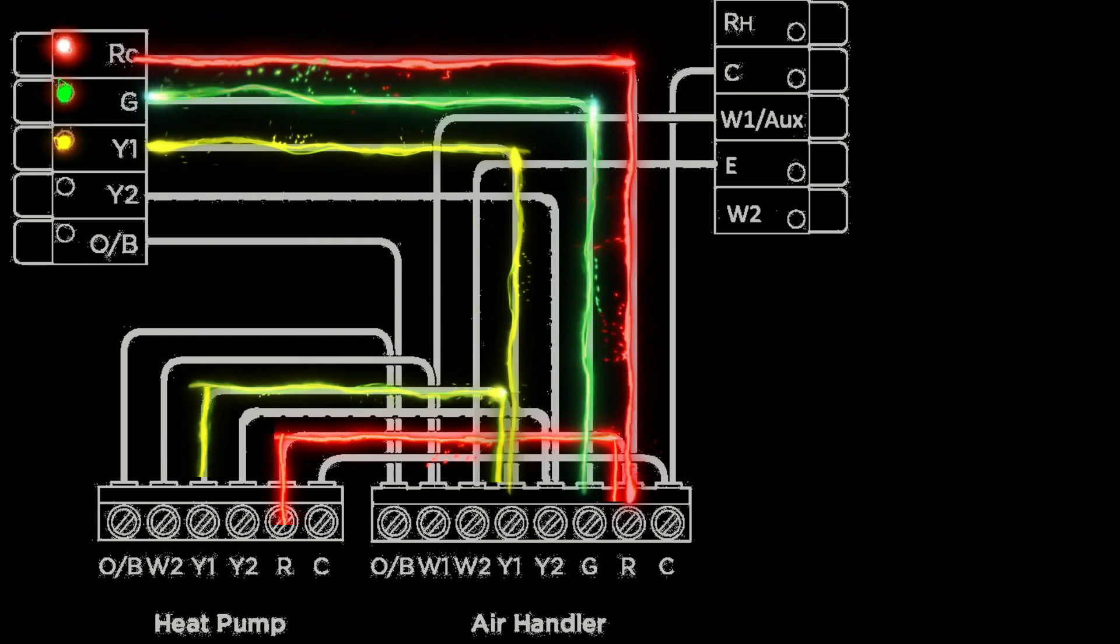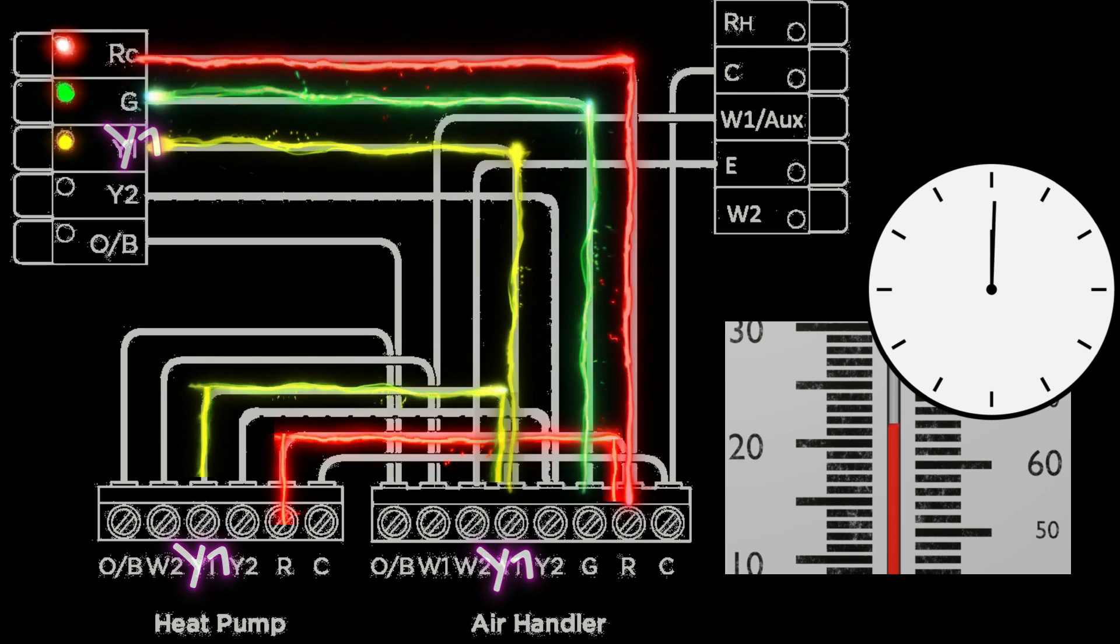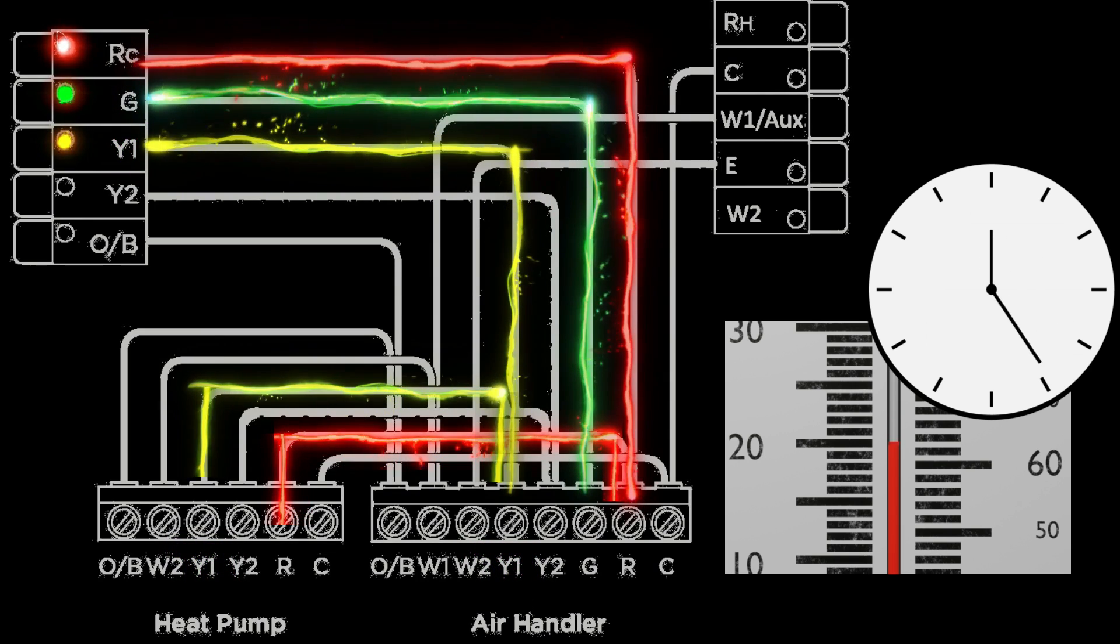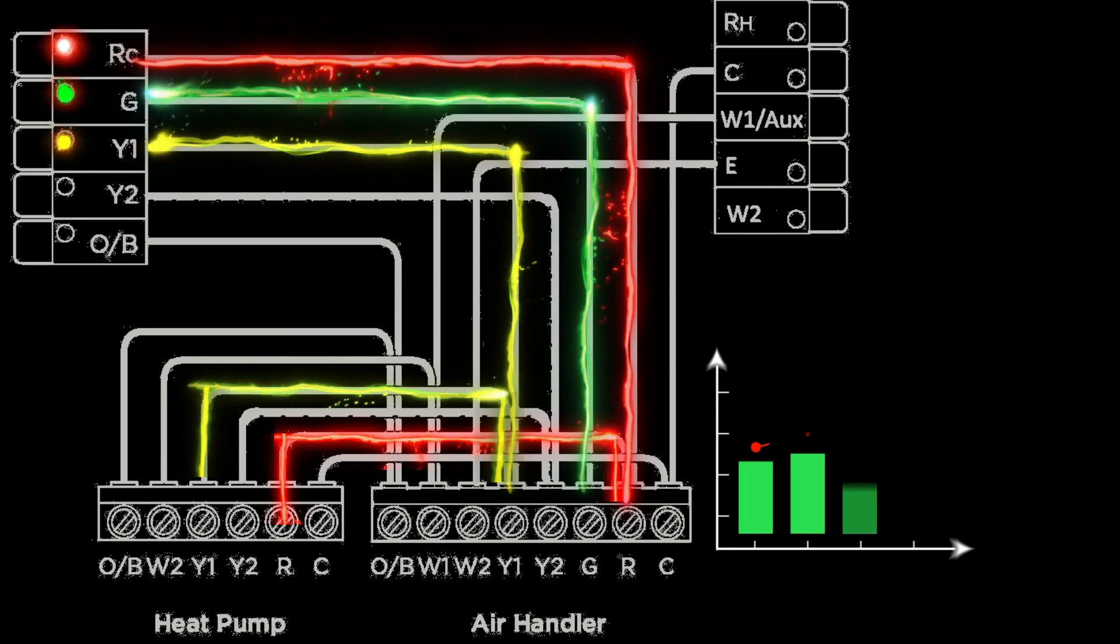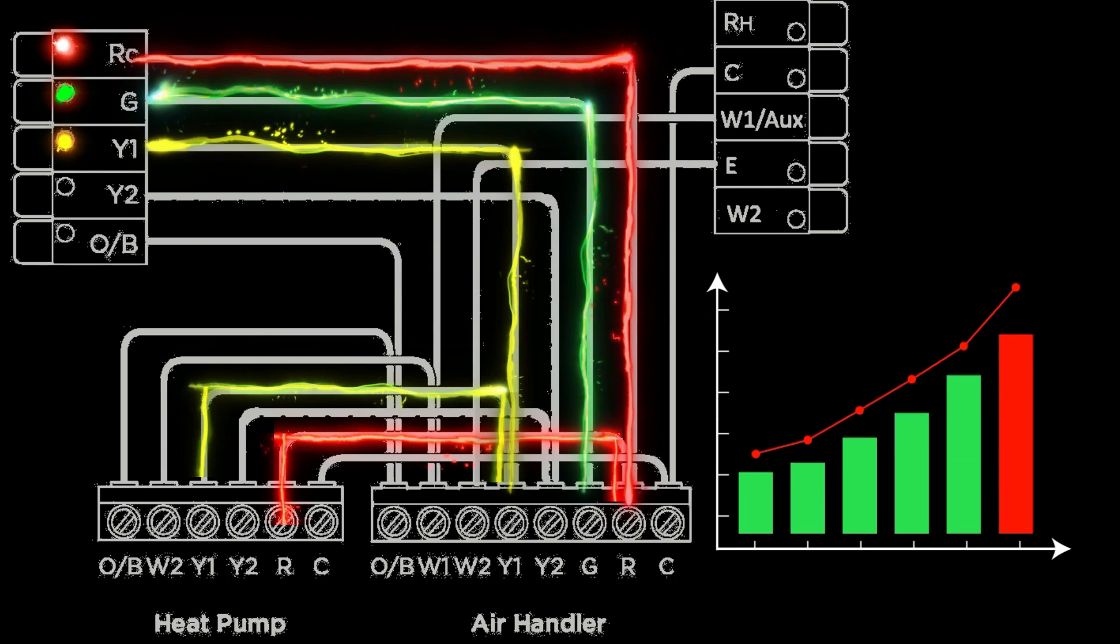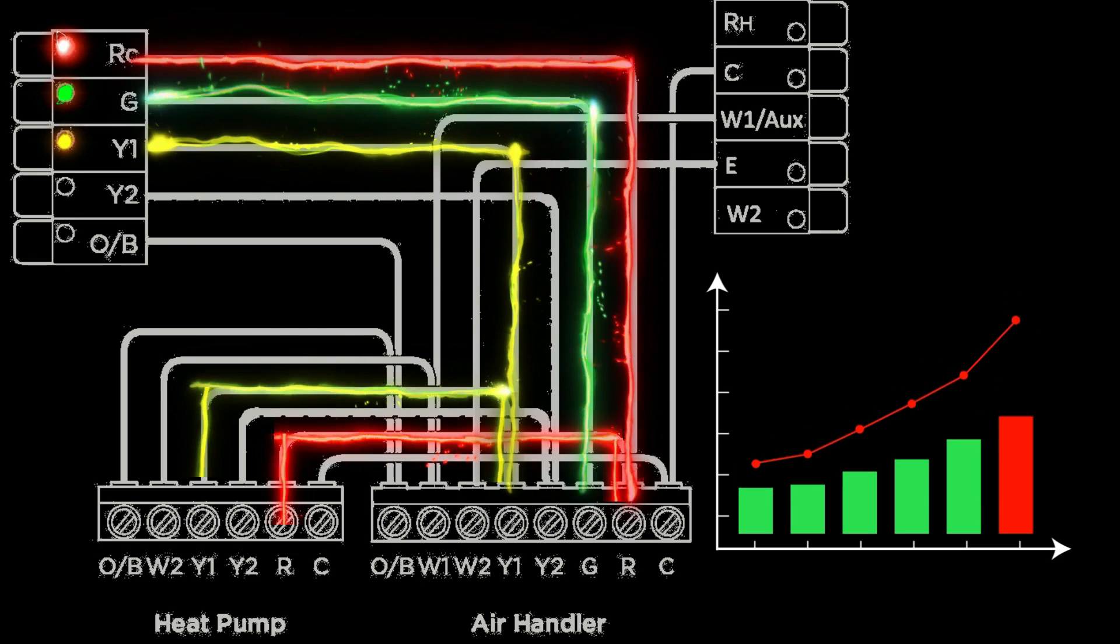So basically what a smart thermostat will do is it will record the temperature every minute and begin plotting these temperatures on a graph. And if the temperature stays within that one degree differential it will continue to maintain first stage.